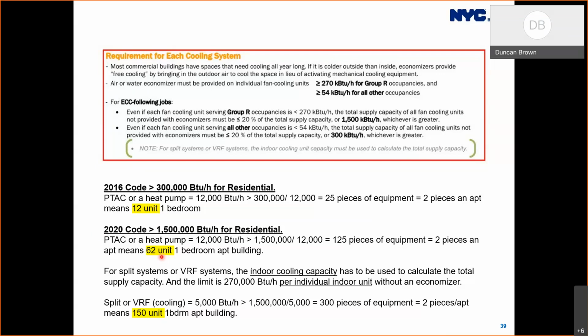And the limit there is 270,000 BTUs per individual indoor unit without an economizer. So the example in that case, where the typical unit is 5,000 and dividing that by 1.5 million, that becomes 300 pieces of equipment. And at 2 pieces an apartment, that also means a 150-unit apartment building. Next slide, please.